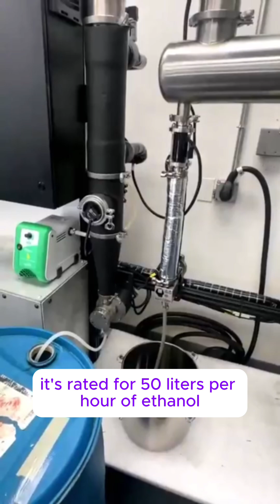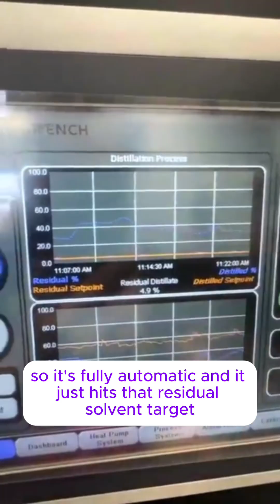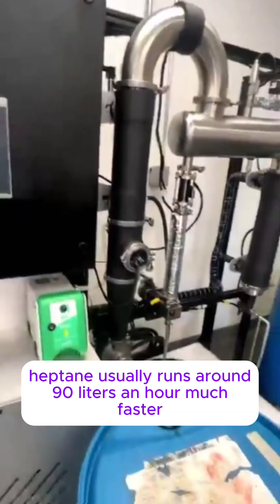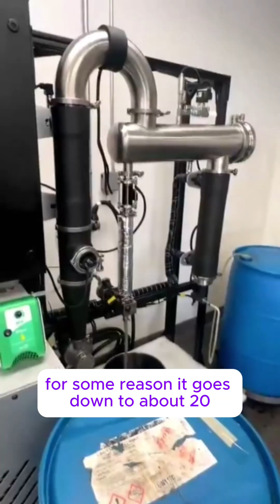60 liters an hour is the top of the system. It's rated for 50 liters per hour of ethanol, and it always runs to the maximum that it can while hitting your residual solvent target. So it's fully automatic, and it just hits that residual solvent target, whatever the rate, and then it can run other solvents. So for example, heptane usually runs around 90 liters an hour, much faster. Or if you distill water on it for some reason, it goes down to about 20 because of the different enthalpies of vaporization.